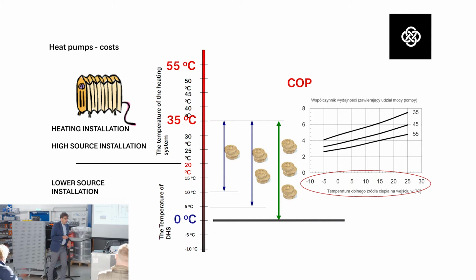What is important to remember regarding this process is that our COP factor is strongly related to the lower heat source temperature. If the lower heat source temperature is lower, the factor goes down, and the cost of operating is growing. So in my mind, we need to follow the rule that the better system is the system with the higher temperature on the lower heat source side.